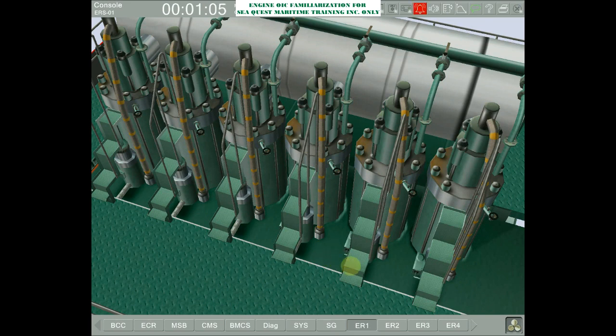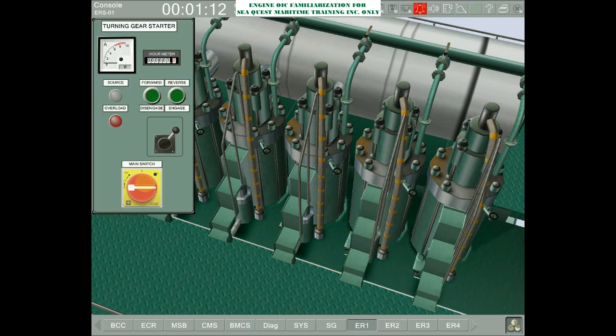go to turning gear LOP, switch on the power supply, and make sure that the selector knob is in the engage side. And then press the forward button for a few seconds, release the forward button, and press the reverse button for a few seconds. Once this has been done, disengage the turning gear, switch off the power switch, and close all indicator valves by using the right button of the mouse.